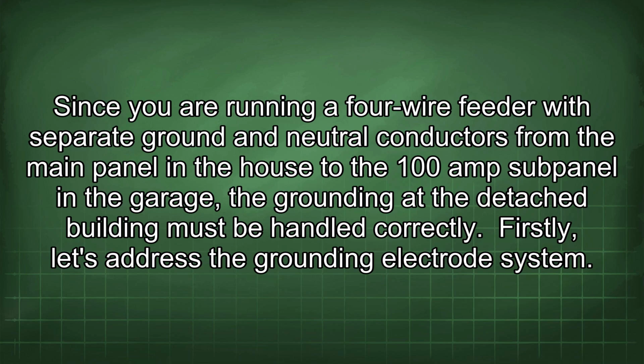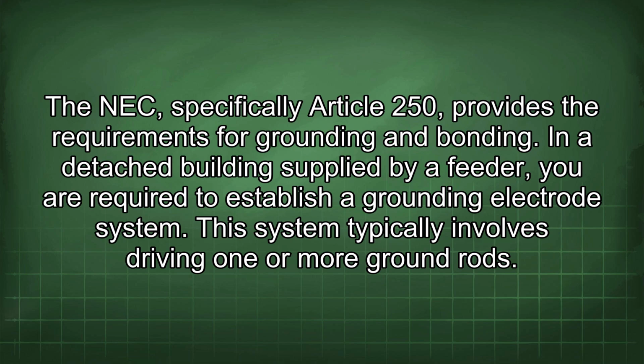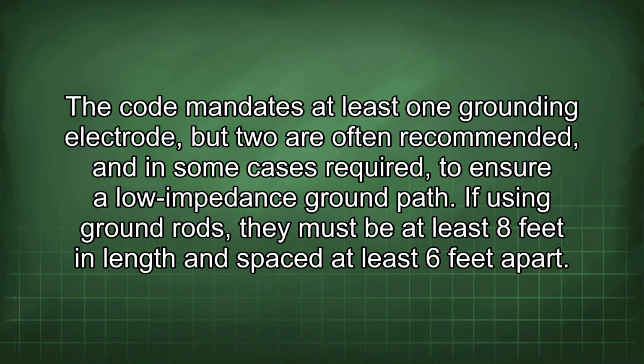Firstly, let's address the grounding electrode system. The NEC, specifically Article 250, provides the requirements for grounding and bonding. In a detached building supplied by a feeder, you are required to establish a grounding electrode system. This system typically involves driving one or more ground rods. The code mandates at least one grounding electrode, but two are often recommended, and in some cases required, to ensure a low impedance ground path.